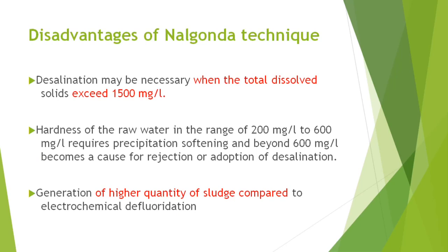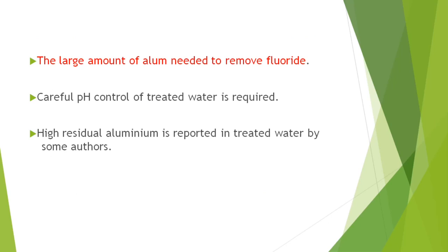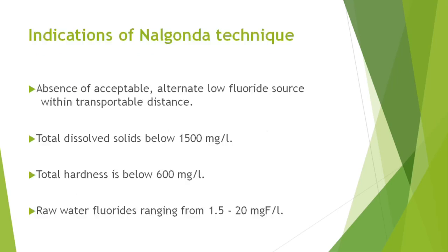The biggest disadvantage is that if total dissolved solids exceed 1500 mg/L, prior desalination is needed. Water hardness also matters: if it is 200 to 600 mg/L it requires precipitation softening, and if it is beyond 600 mg/L it may require desalination. There will also be a high amount of sludge compared to other methods. Indications: total dissolved solids should be less than 1500 mg/L, total hardness below 600 mg/L, and raw water fluoride should be between 1.5 to 20 ppm.